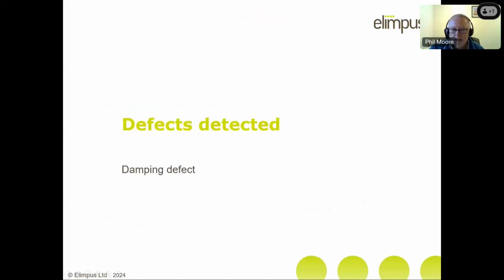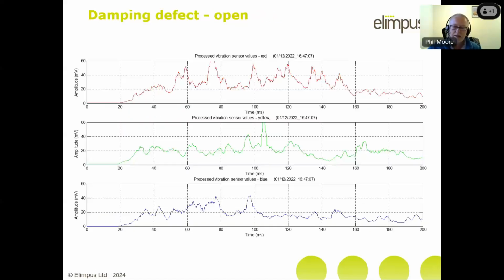And finally, this is my last slide now. This is to do with damping. So just a word or two about damping. When the contacts open, they initially accelerate and they move at a constant speed. And as they get towards their maximum position, you have to slow them down, otherwise they'll hit the end stops and they'll rattle the breaker apart.